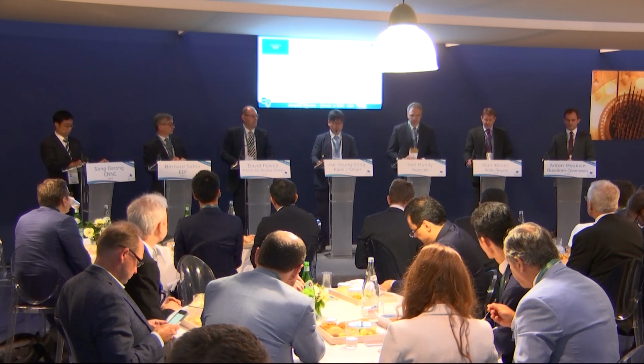And then lastly, that strong safety case in terms of the environmental impact. It's important for our design to be able to be sited near demand centers for the offtake of that electricity and that heat, and also in areas where the population densities are probably higher than had been previously approved. Our small cores, small source term, less radioactive material, less release associated with that, results in our ability to justify the approval of a site boundary emergency planning zone. So this emergency planning zone ends at the boundary of our facility, not 10 miles out as currently approved by the NRC. Thank you, Tom.